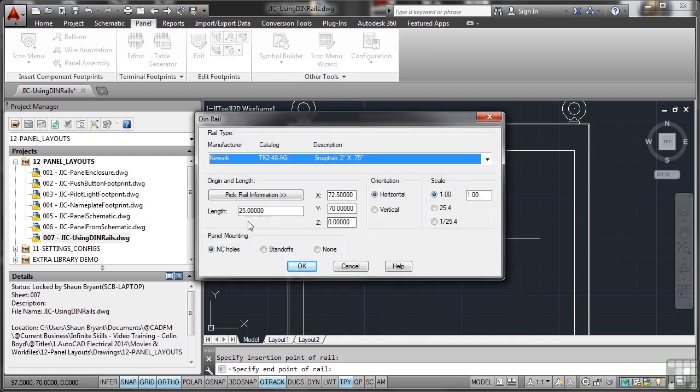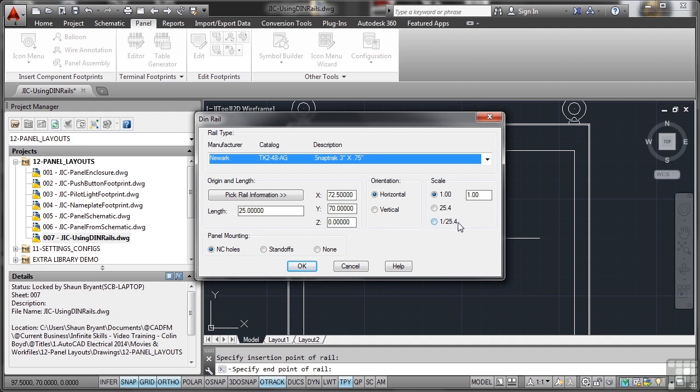So the length of that is 25 inches long and it's going to be obviously horizontal because the line is horizontal and the scale is one to one. Now in this particular case, obviously if I've got a metric one that I want to use, let's say on an imperial drawing, I can set the scale 1 divided by 25.4 and that will give me the right ratio and scale it accordingly. So those settings are really useful. I can use imperial or metric on any given panel drawing in any given AutoCAD electrical project.